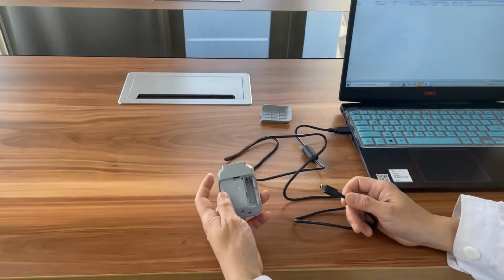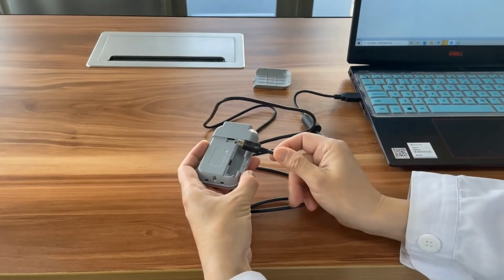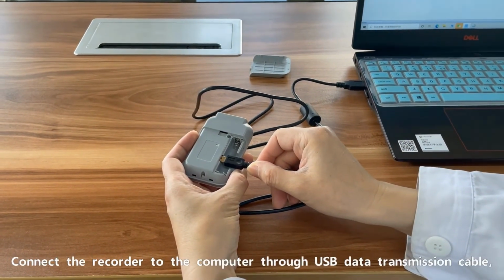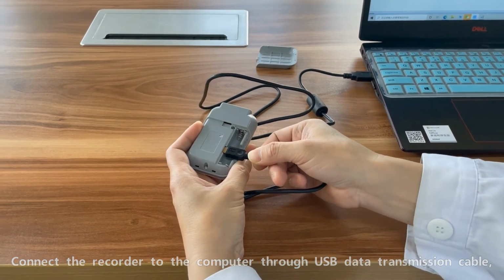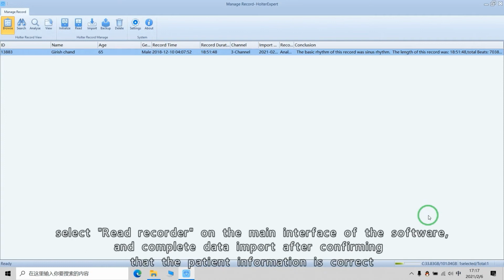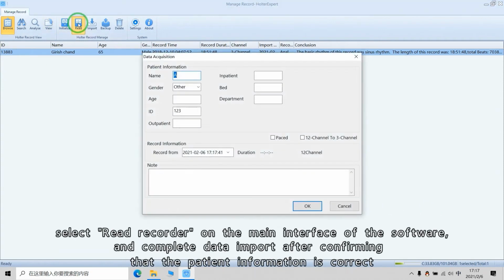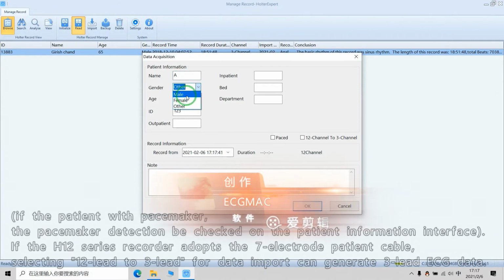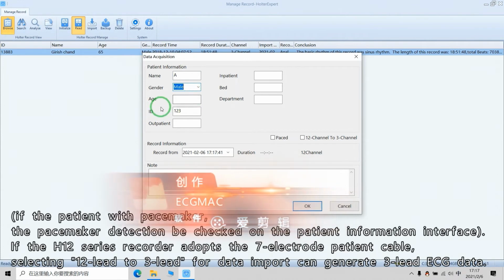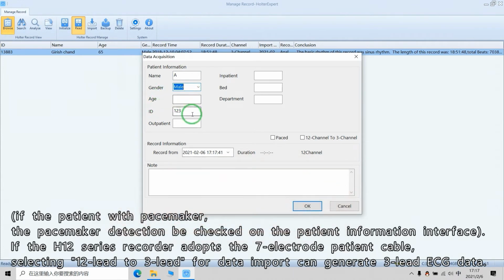Data import. Connect the recorder to the computer through the USB data transmission cable. Select Read Recorder on the main interface of the software, and complete data import after confirming that the patient information is correct. If the patient has a pacemaker, pacemaker detection should be checked on the patient information interface. If the H12 series recorder adopts the 7-electrode patient cable, selecting 12 lead to 3 lead for data import can generate 3-lead ECG data.